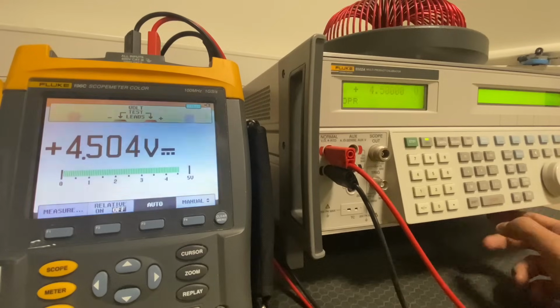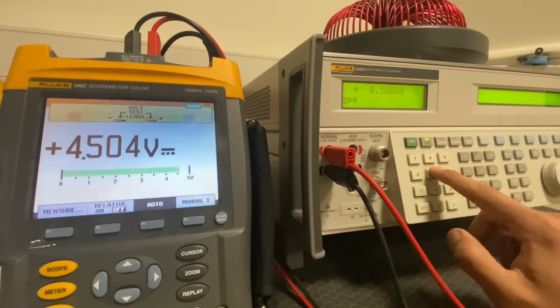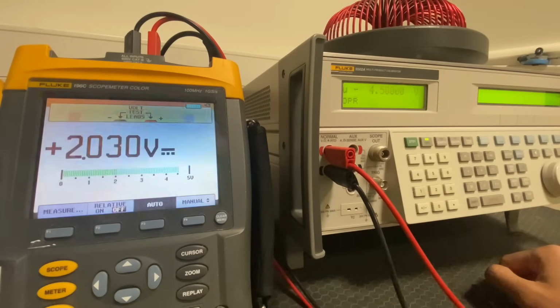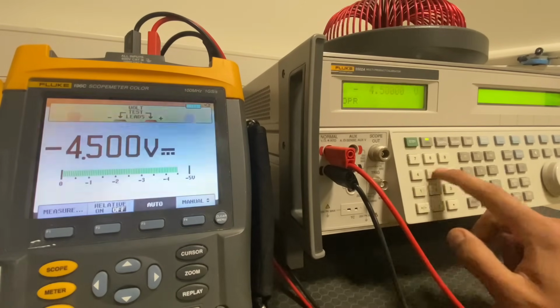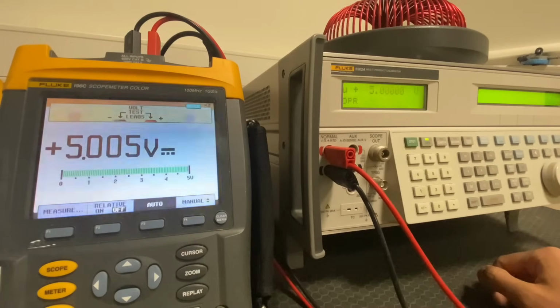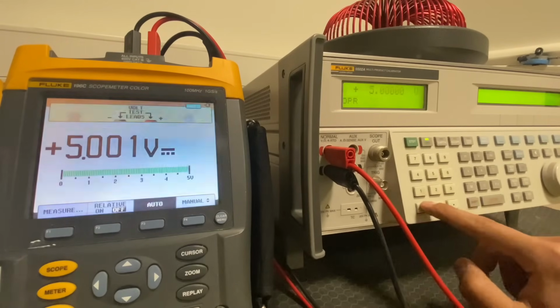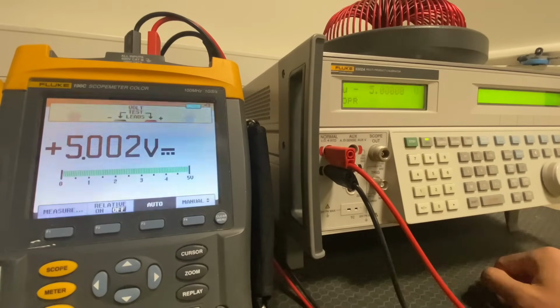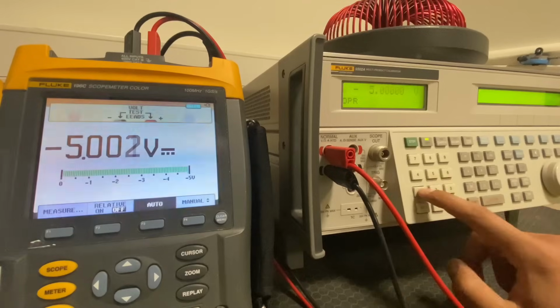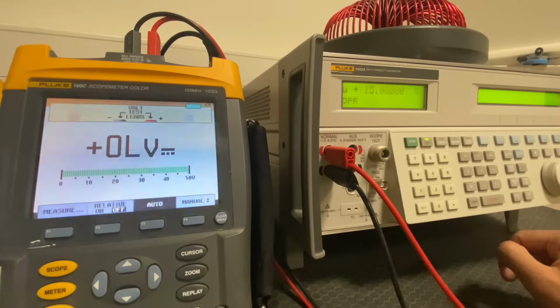It's important to check two negative measurements when performing DC voltage calibration. There may be deviation at these values. To address this, search for the oscilloscope's brand and model online to find its datasheet. Then ensure that any tolerance range specified in the datasheet is included in the certificate.